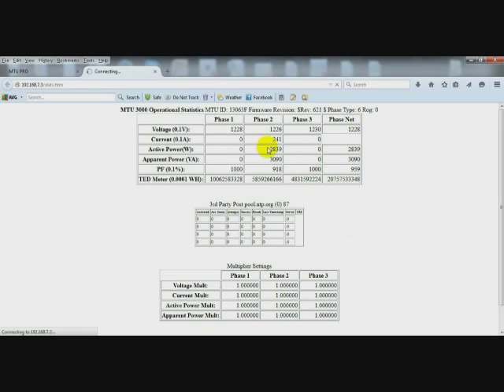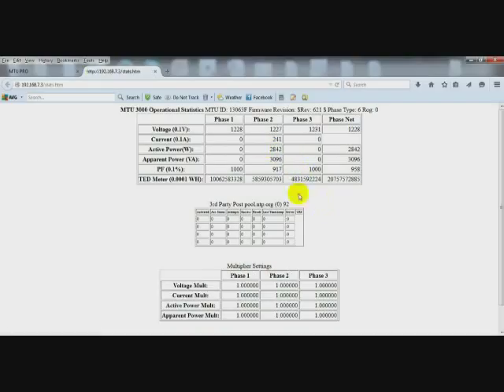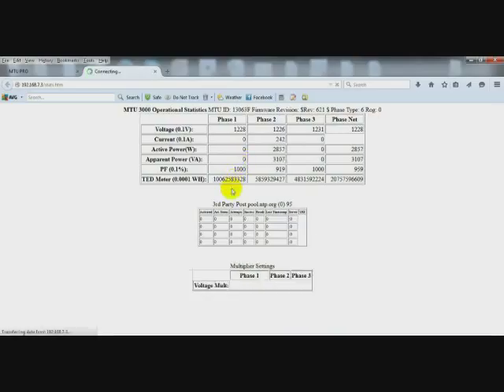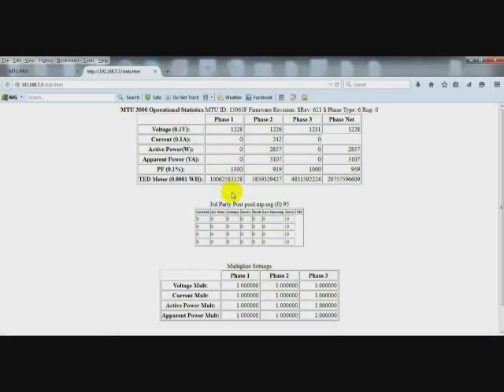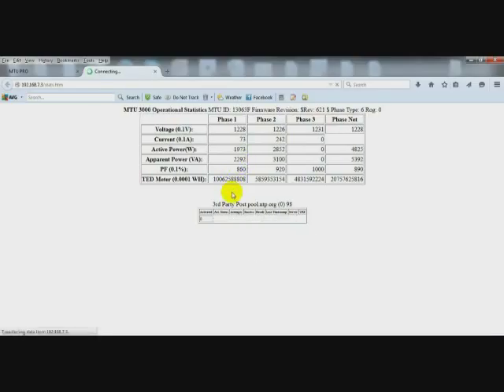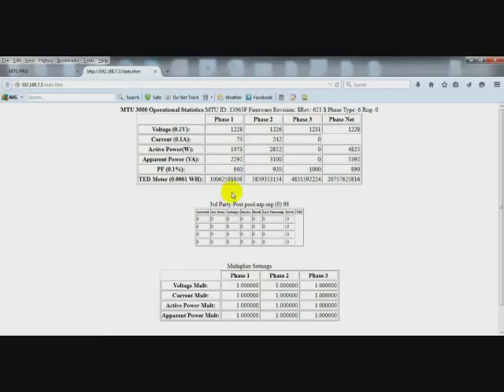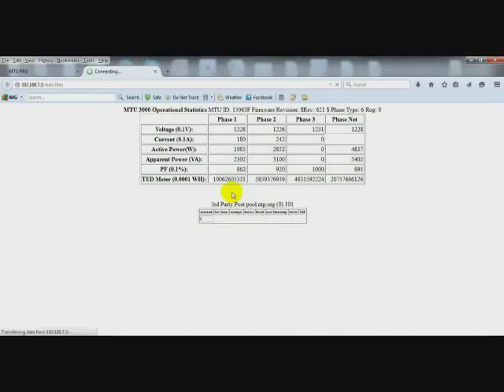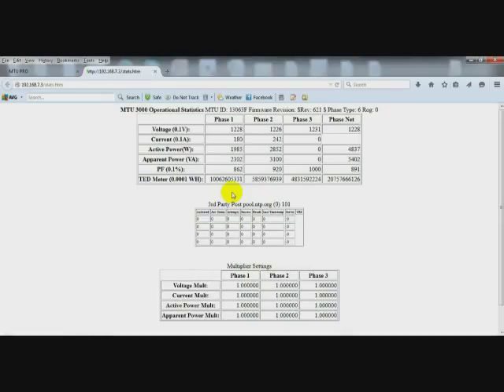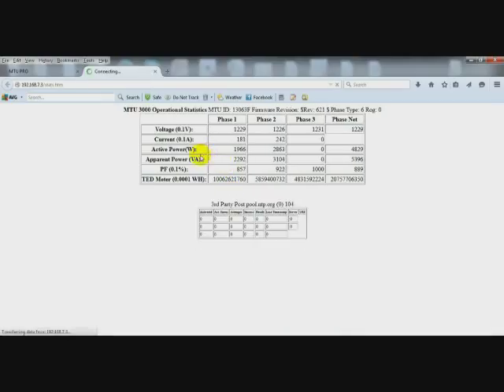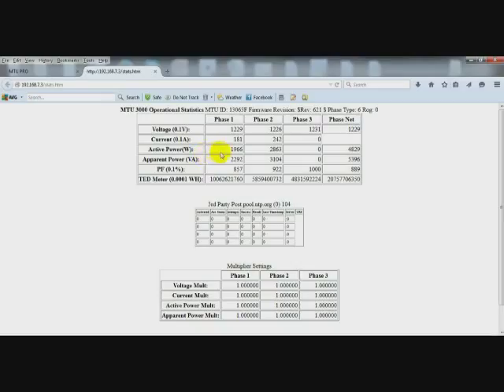Since we now have a positive number for active power on phase B or phase 2, we will just try the CT connection in phase A, if it's correct. Okay. We see that we now have a positive number for active power, phase A, as well as a reasonable power factor for both A and B.